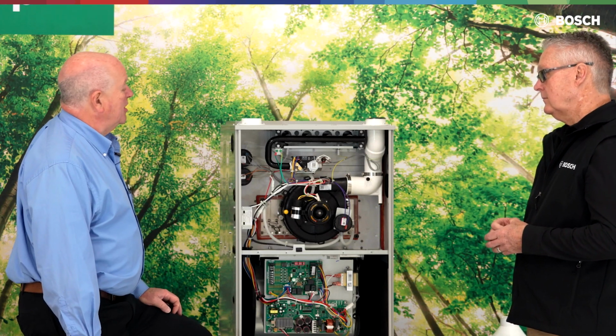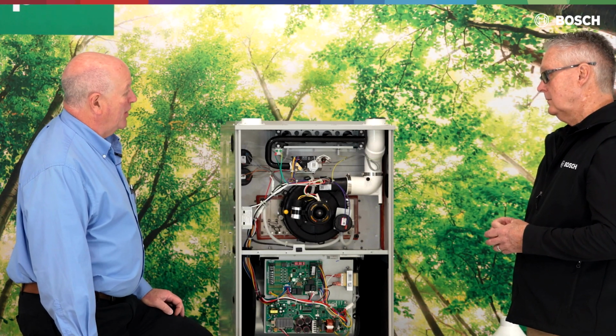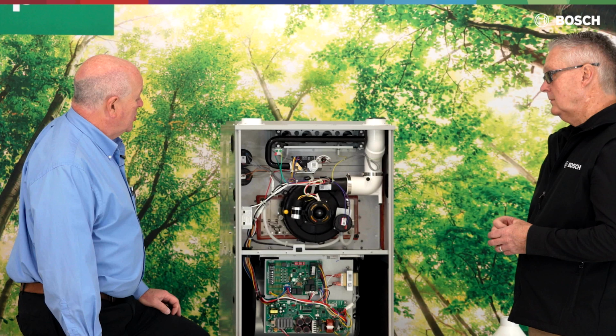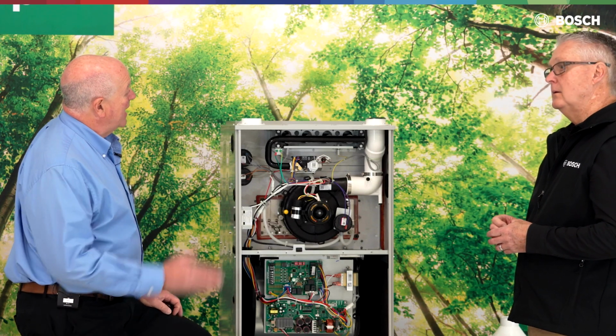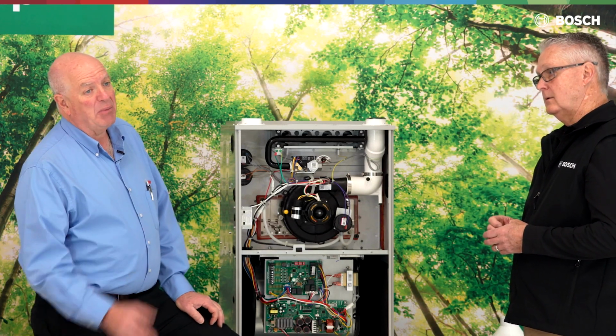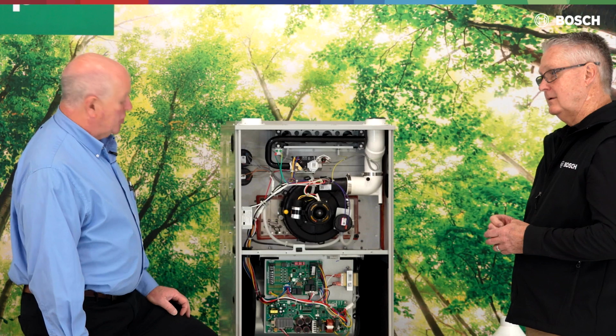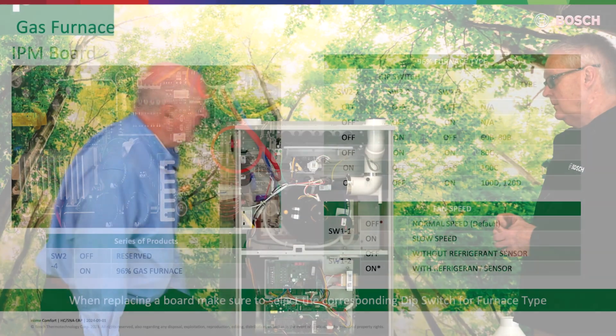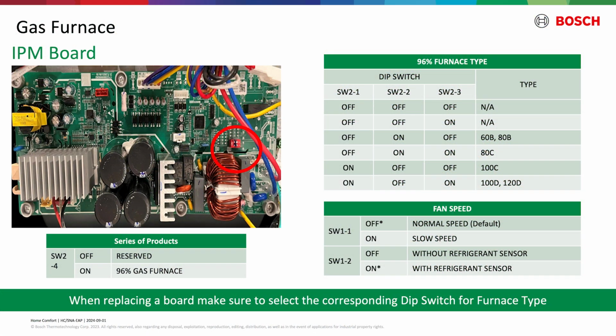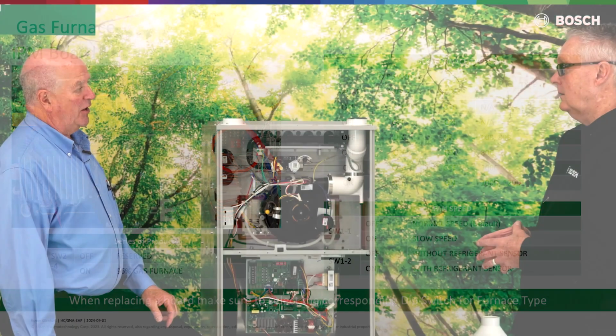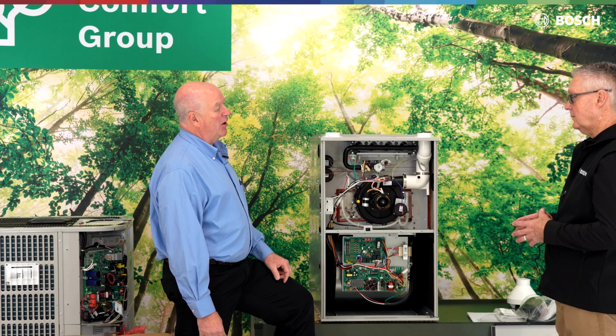Yep. If you have a dirty filter, if we don't have the proper airflow going through the system, if we choose the wrong fan speed, and guys, something new on this one is we have one replacement board. So in the future, if you have to replace the lower board, that one board fits all of our units. Look at that. And you have to choose the proper CFM for the unit you're sizing. If we choose a 60,000 BTU setting on the board and it's a 120, we're going to have half the airflow. It'll be popping off on high limit all the time.